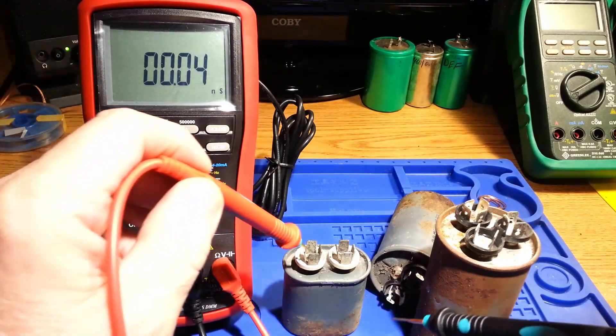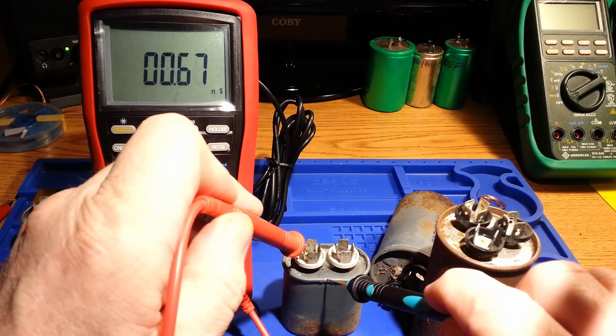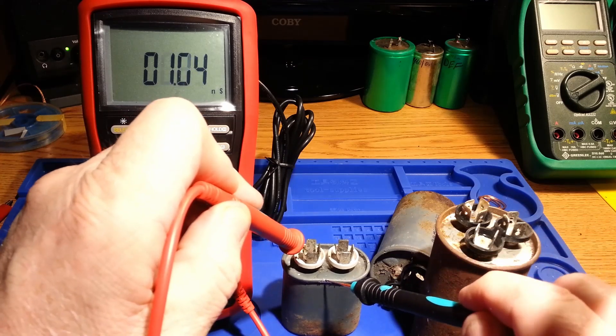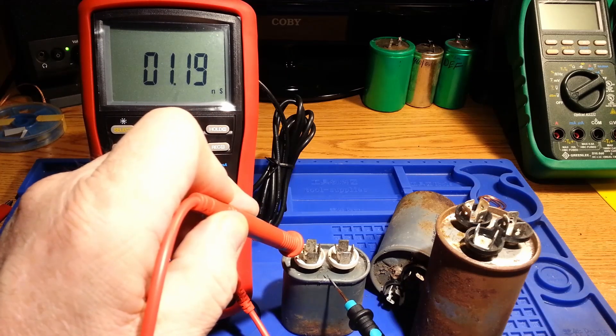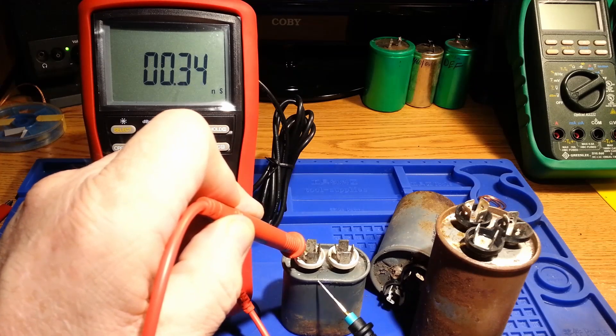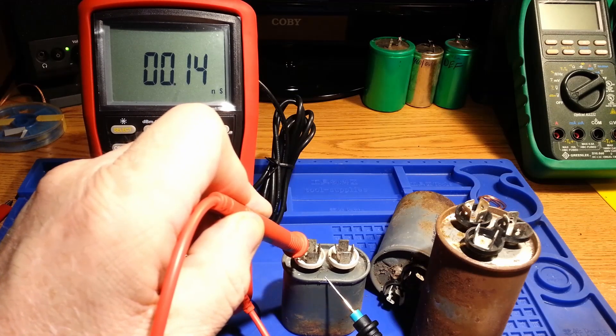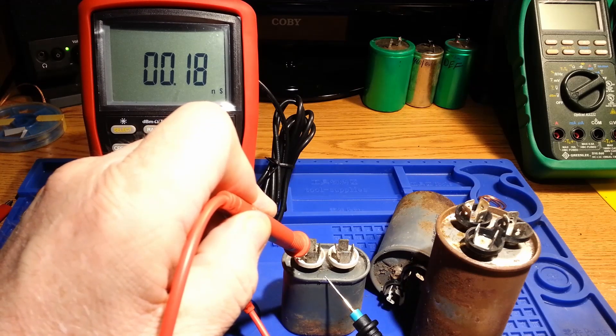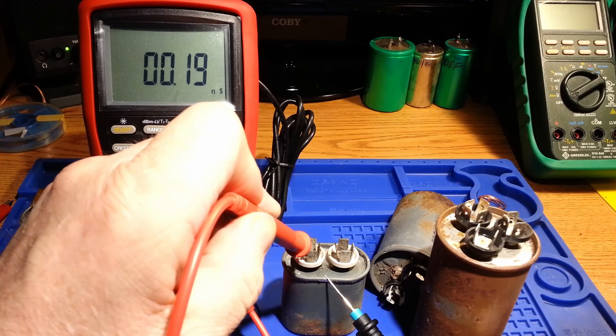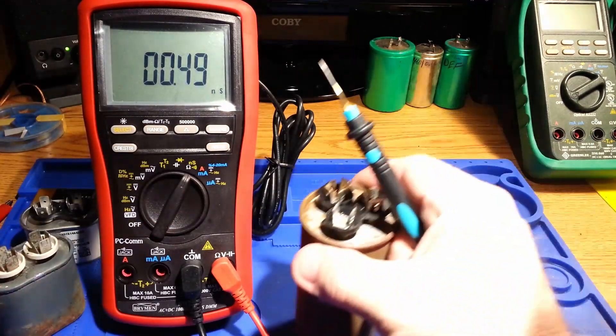So we'll go with this capacitor. You see this one's coming up with a higher conductance value. It's not really willing to get down all the way down to that 0.02. Well, it settles out at about a 0.2, which measures out to about five gigaohms.